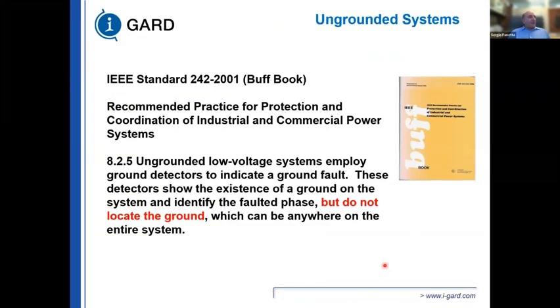Some of the standards that are out there: the Buff Book, IEEE Standard 242, 2001, says that ungrounded low voltage systems employ ground detectors to indicate the ground fault. These detectors show existence of a ground fault but do not locate it. Again, the only way you can locate the ground fault on an ungrounded system is to cycle the power on individual breakers until you find the presence of that fault. You have ground fault detection. When that ground fault detection goes away, you keep following that path downstream to find where the ground fault is.